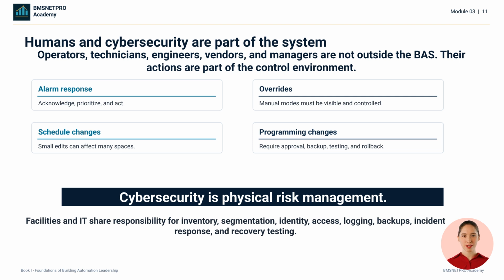Humans are part of the system. Operators acknowledge alarms, technicians place equipment in manual, engineers change logic, vendors access systems remotely, managers approve risk. A design that ignores how people actually work will create workarounds. Cybersecurity is also physical risk management because digital actions can affect physical conditions. Facilities and IT must share responsibility for asset inventory, segmentation, identity, remote access, configuration, logging, backup protection, incident response, and recovery testing.